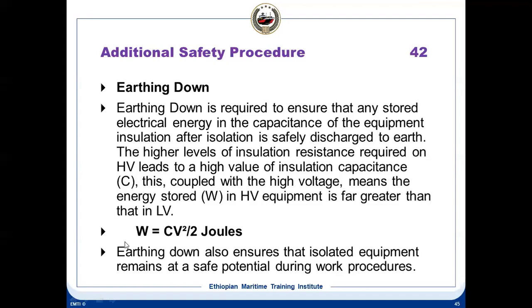So you have to earth down to discharge any residual charges, because this is a capacitance property of the cable. If you see a cable, it has a capacitance property because it stores some charges, because it has insulators inside. So electric energy in the capacitance of equipment insulation after isolation is safely discharged. Earthing down ensures that isolated equipment remains at a safe potential during the work procedure.